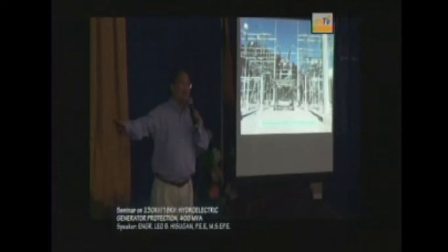So this circuit breaker here is elevated around 10 feet above the ground. So I have a circuit breaker, and we put a platform 10 feet above the ground because during winter time, all of these are all filled with snow. So we cannot operate the breaker if there's snow, right? So we have to raise the circuit breaker 10 feet above the ground. Can you imagine that? And going to the substation, 10,500 feet above sea level, we have to use snowmobile or catmobile to go there.